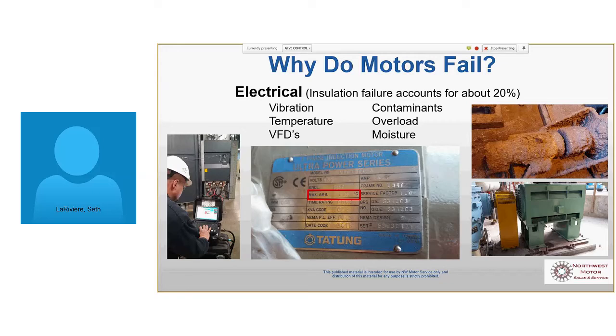Certainly when a motor's at the top of a roof, underneath the ceiling, heat rises, the motor's often way hotter up there than it is even on the plant floor. It might be 80 down below, but it's going to be 120 up there. So there are a lot of different things that can introduce heat to a motor. You might have a high ambient. The motor might be on a drive. A drive tries to simulate a real nice sine wave, but if you look at it, it's a bunch of little choppy spikes that make that sine wave, and those are harmonics, and they introduce heat into the motor. So if a motor's on a VFD, it's going to run hotter than it would across the line. So that's another consideration.